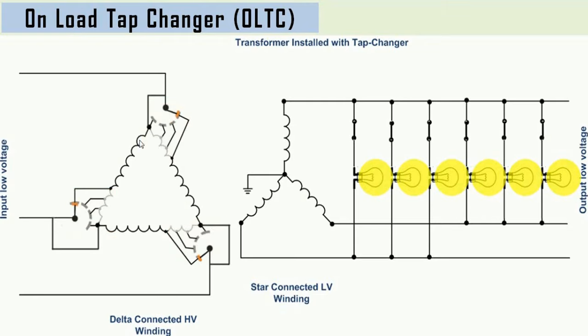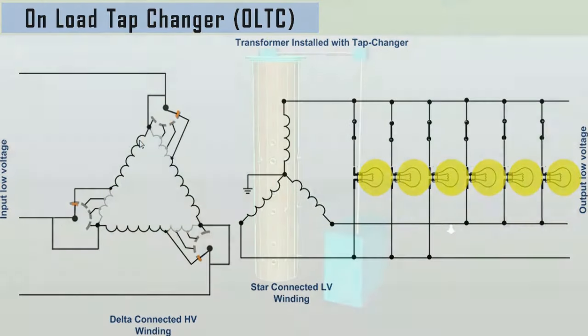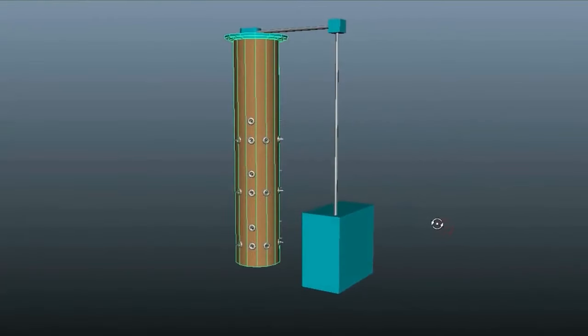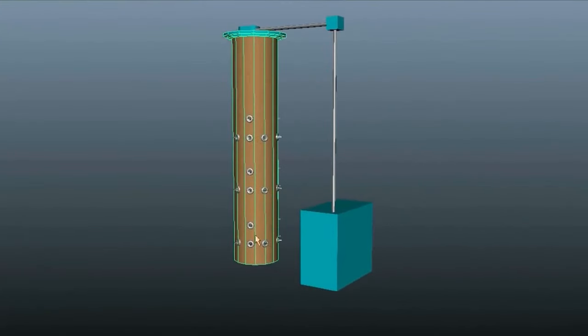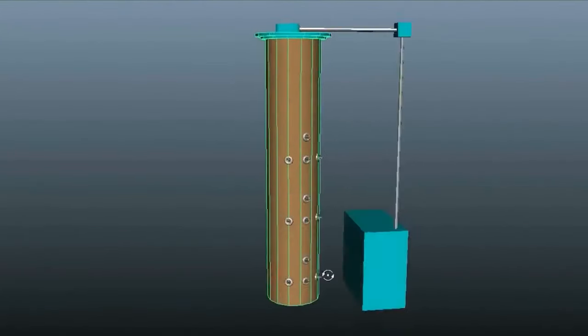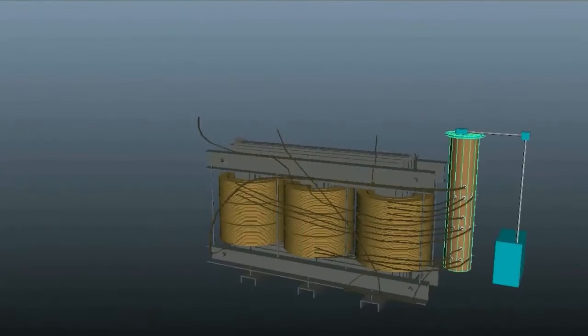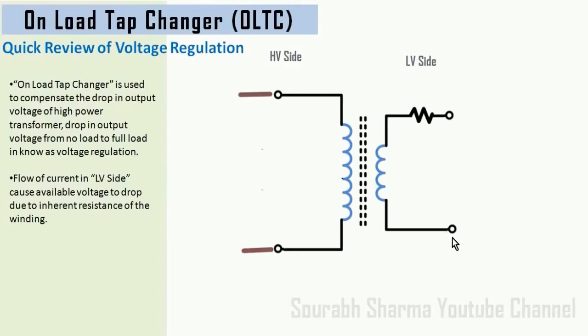The variation of terminal voltage can be restricted near to the expected value by changing the tap position in the transformer winding. And this can be done without making the transformer off, by the help of a cylindrical device — that is the On-Load Tap Changer, or in short, OLTC. The device is generally, but not necessarily, installed inside the transformer tank along with the winding assembly, and it is always connected to the high voltage winding. Before going into its detail, let's have a fair understanding of voltage regulation.